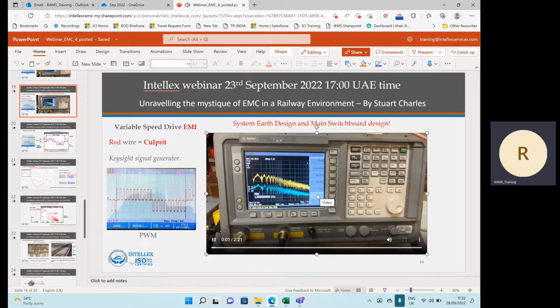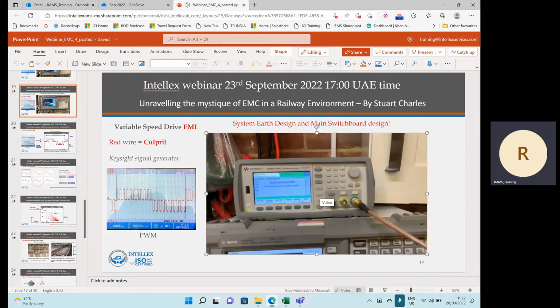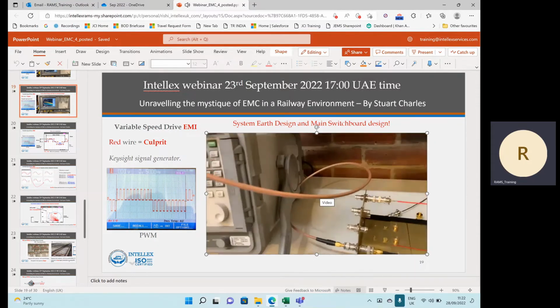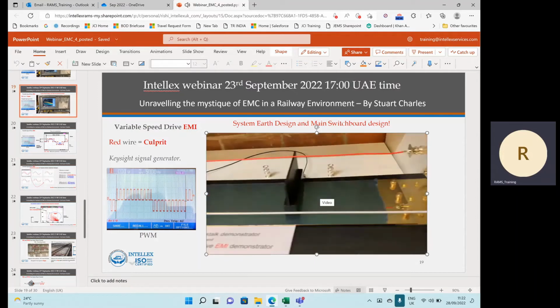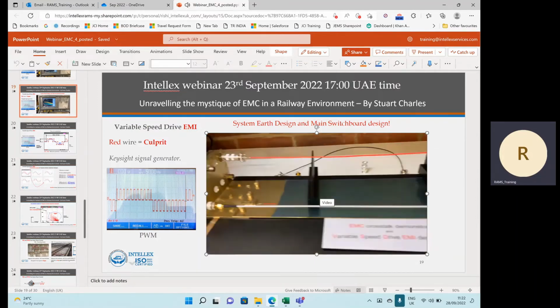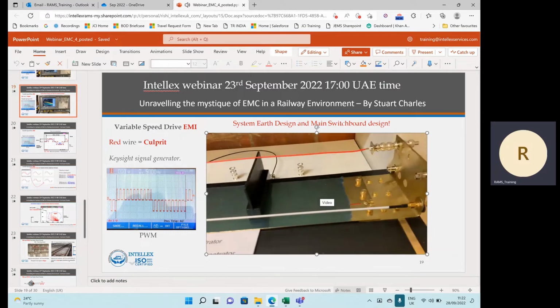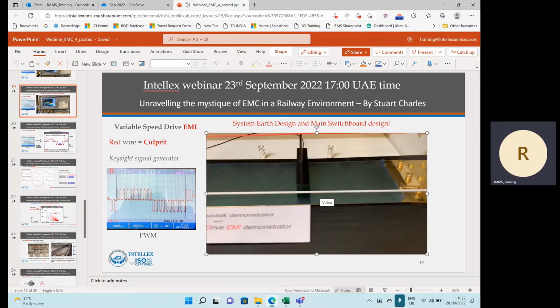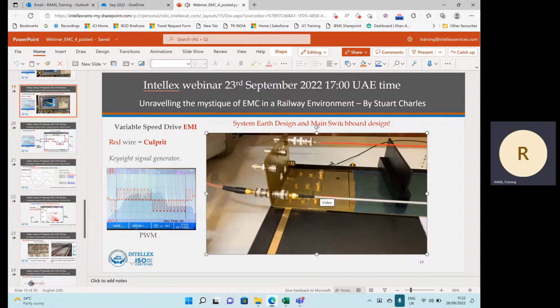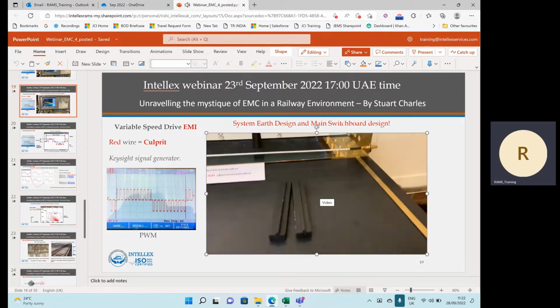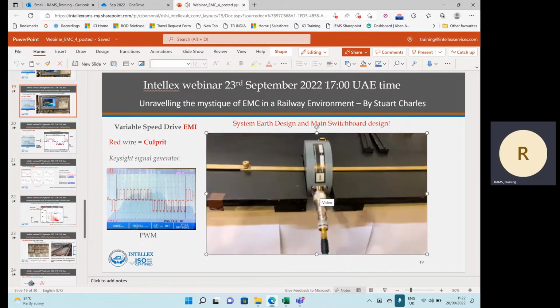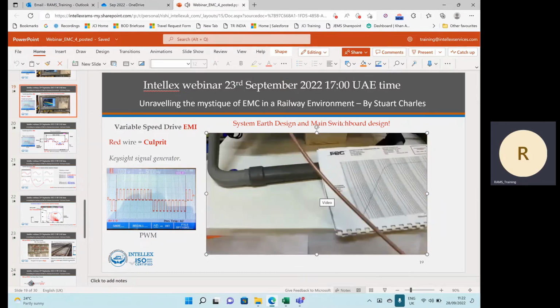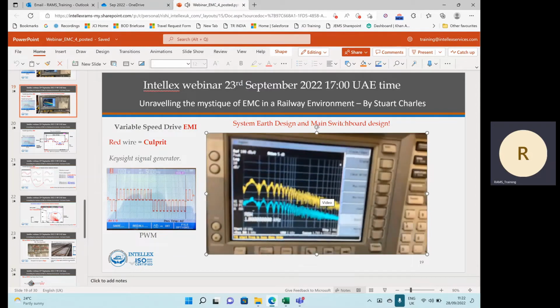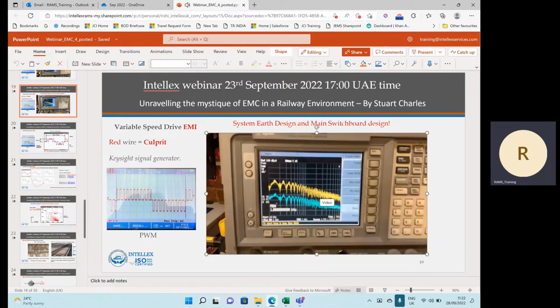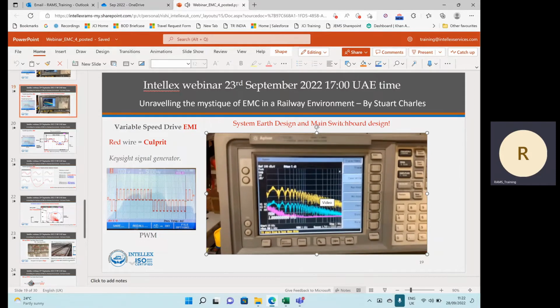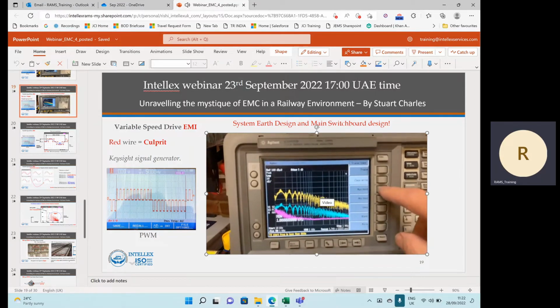In part 3 of the video, what we're now doing is driving our simulated VSD output down a screened cable. It's the 50 ohm termination, so the current is flowing down the center conductor of the coax and returning through the braided screen. Again, we're looking at how much contamination in terms of current flows through the external system earth. So again, I need to go on to trace number 3, which I'm already on, and I need to clear write it, and then I'm going to max hold it.